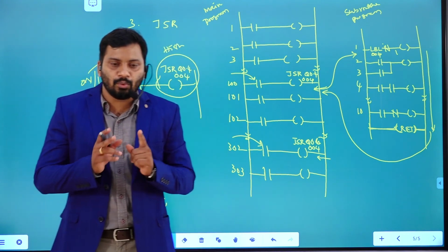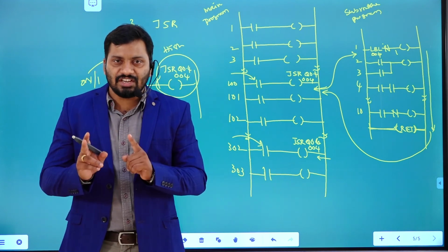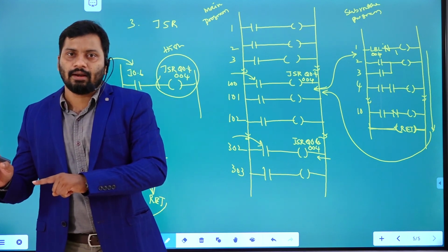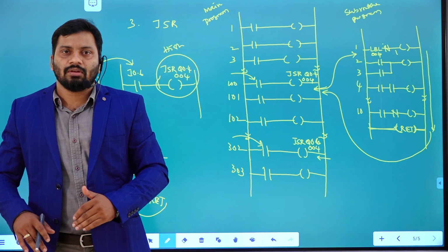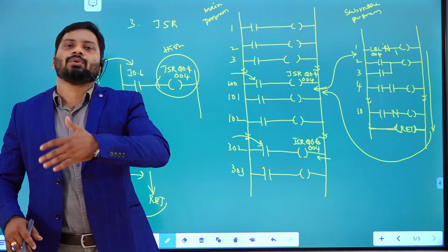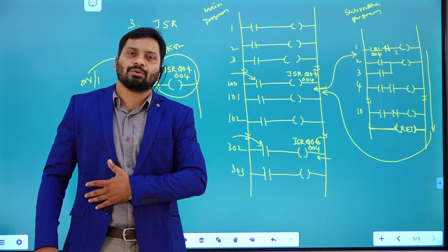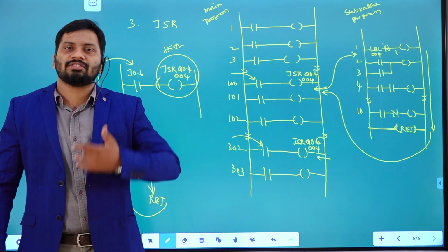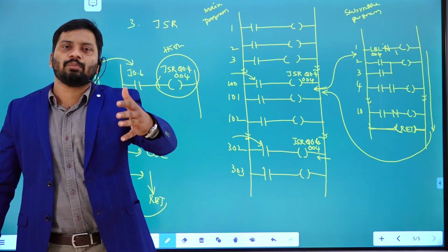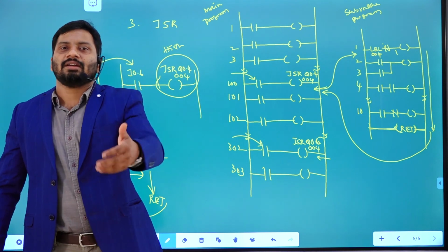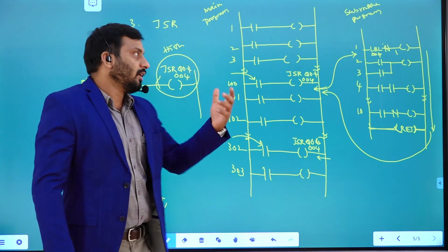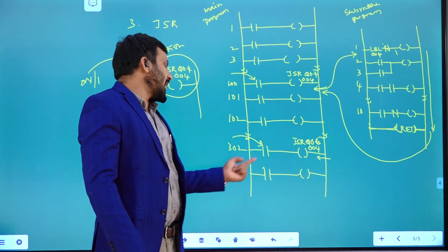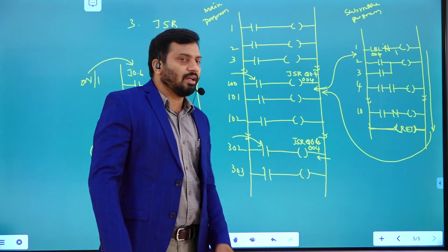Here you need to remember two labels, JMP and JSR. JMP means it is jumping only. Once it has jumped, it is not going to execute the next instruction. It jumps to the label address, and from there it executes. It's not getting back. Jump with subroutine means it jumps to the subroutine. After execution of the subroutine program, whenever the return rung is come across, it jumps back to where it was stopped. Here it's jumping means it returns back to 101. Here it is jumping means it returns back to 303. Then it keeps on executing the main program.